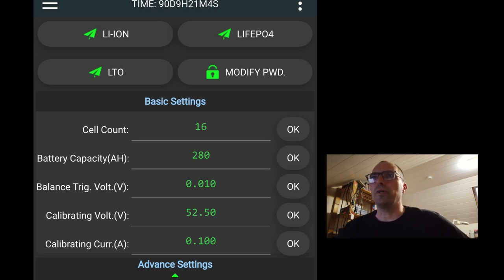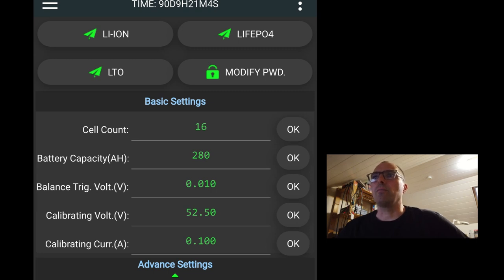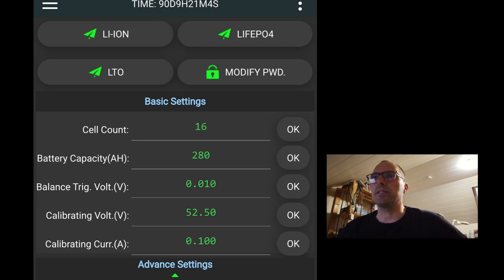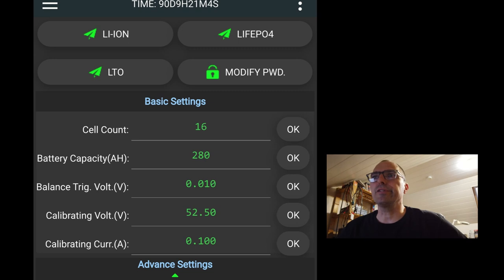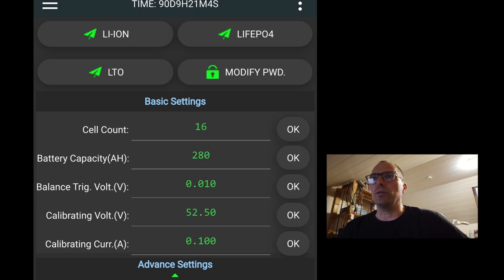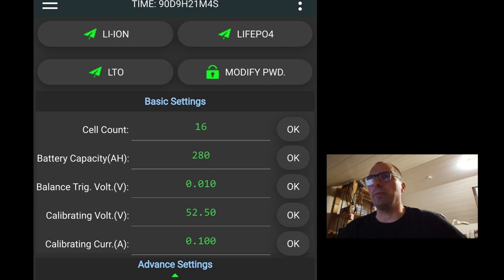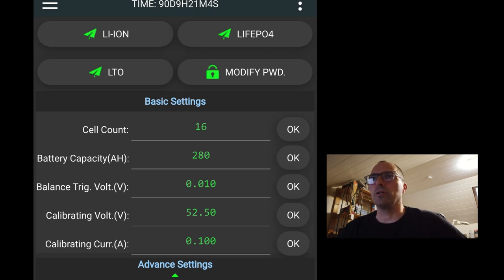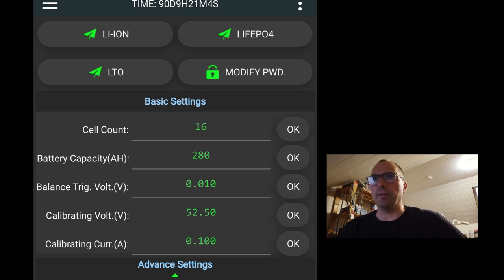Let's go over the basic settings of the advanced menu. Most of these settings are already entered. So the cell count is 16. The battery capacity is 280 amp-hours. The balanced trigger voltage is 10 millivolt. The calibrating voltage. So if you measure the voltage of the pack and you compare it with the voltage measured by the BMS, there might be some unbalance. And here you can enter the voltage you measured on the battery tabs. And the calibrating current.